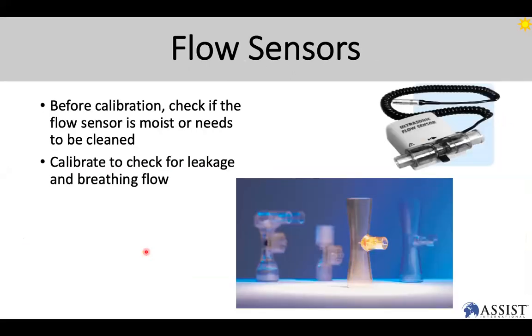Flow sensors are another component of the ventilators that need to be looked at. Before you calibrate a flow sensor, you must always check to see if it is moist or if it needs to be cleaned. Especially in anesthesia machines or ventilators where there has been an accumulation of moisture, flow sensors will be degraded. And so you want to pay very close attention to your flow sensors. Make sure that these are clean and there's no moisture, as it'll cause damage.